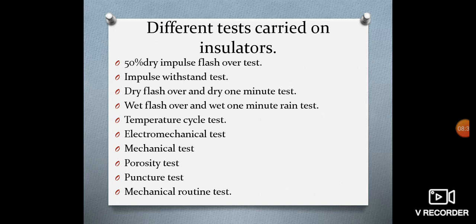Now we will understand about the temperature cycle test. The insulator is immersed in a hot water bath whose temperature is 70 degrees centigrade, higher than the normal water bath, for T minutes, capital T minutes. It is then taken out and immediately immersed in a normal water bath for T minutes. After T minutes, the insulator is again immersed in the hot water bath for T minutes. The cycle is repeated 3 times and it is expected that the insulator should withstand the test without damage to the insulator or glaze. Here T equals 15 plus W by 1.36, where W is the weight of the insulator in kilograms.